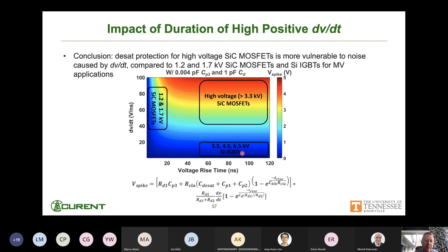So you have to withstand a high dV/dt for quite a few nanoseconds. This region of high dV/dt combined with long voltage rise time is something we don't see in other devices—not with silicon IGBTs, which also have a long rise time but aren't as fast, and not with lower voltage silicon carbide MOSFETs, which are very fast but operate at lower voltages so the rise isn't as long. This is something I wanted to highlight, a concern specific to these 10 kilovolt silicon carbide MOSFETs that you need to design for and be prepared for, unlike with low voltage devices or high voltage silicon devices.